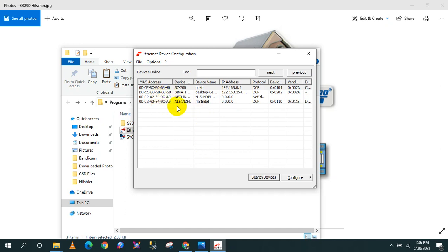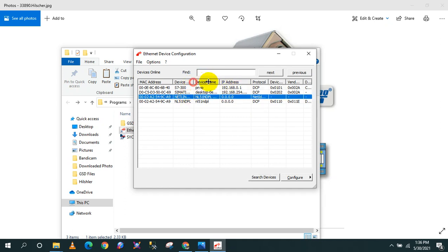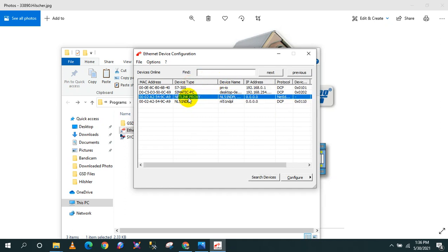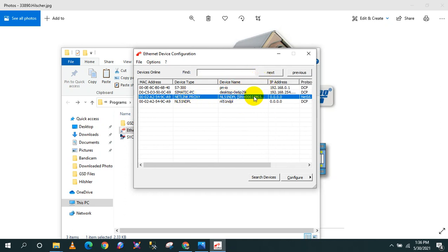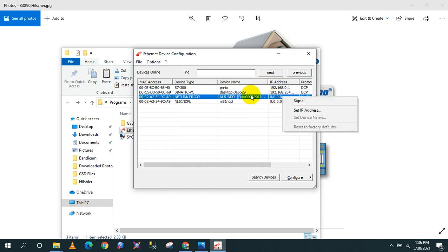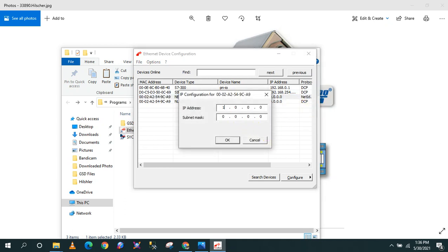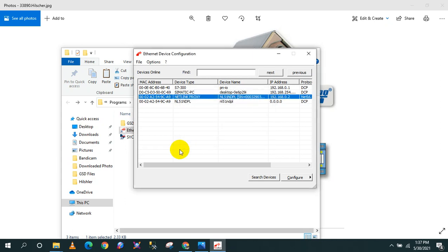As you can see, it browsed four different ethernet devices here. All you have to do is locate the Netlink Proxy. This is the device that is going to convert the PROFIBUS into PROFINET. As you can see, it has a default of 0.0.0.0, so we need to assign an IP address for this. I'm going to put 192.168.0.2, subnet mask, click OK. Now it's already been configured. Just click minimize.